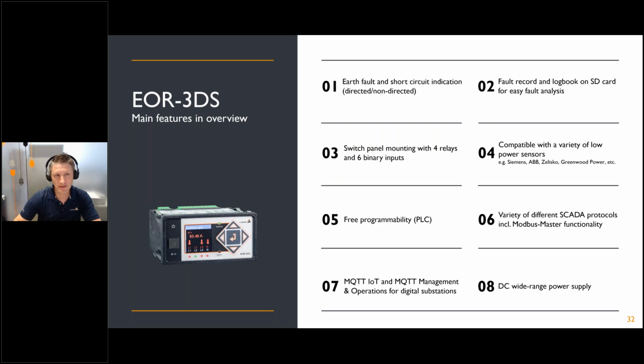A short overview, like I showed you from the EOR-1DS. We have all earth fault and short circuit methods on board, directed and non-directed. We have fault records and logbooks on the device, of course, and they can also be read out via software. We have a dedicated software for the EOR-3DS. It has 4 relays and 6 binary inputs, which is quite important to fulfill the switching requirement in these digital secondary substations. We are compatible with a wide range of low power sensors, even more than with the EOR-1DS. You remember the EOR-1DS was only capable of sensors with 2-wire connection. The EOR-3DS can also connect sensors with RJ45 plug.